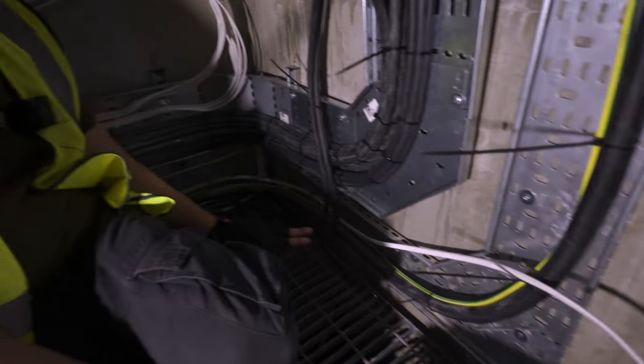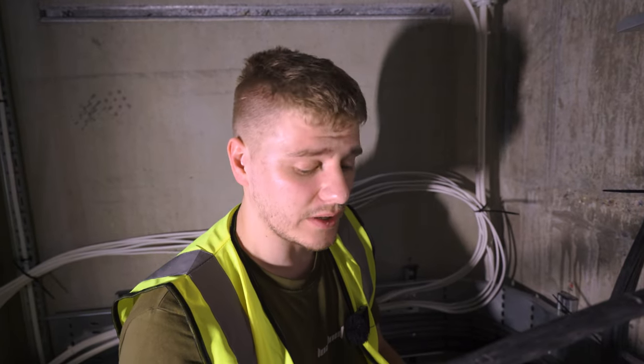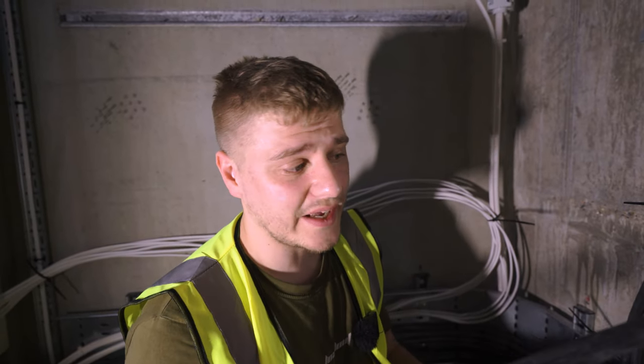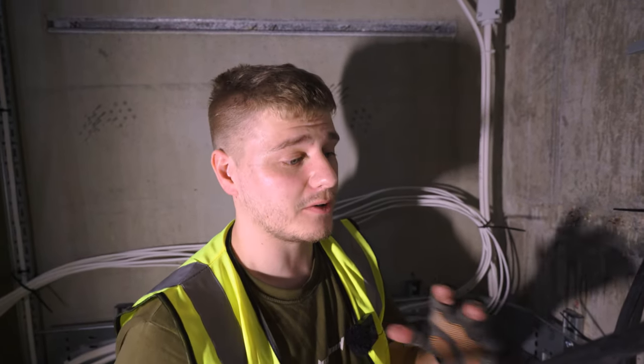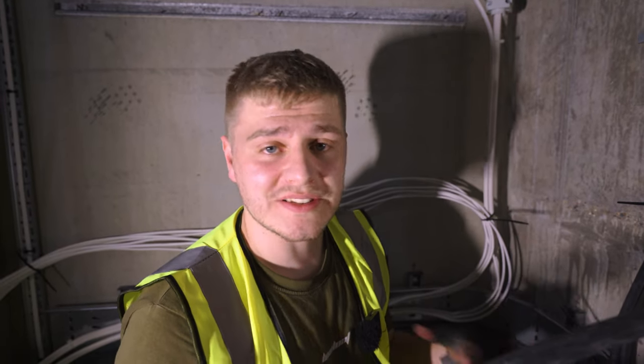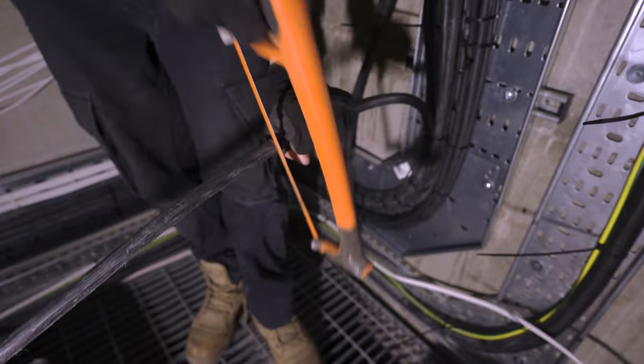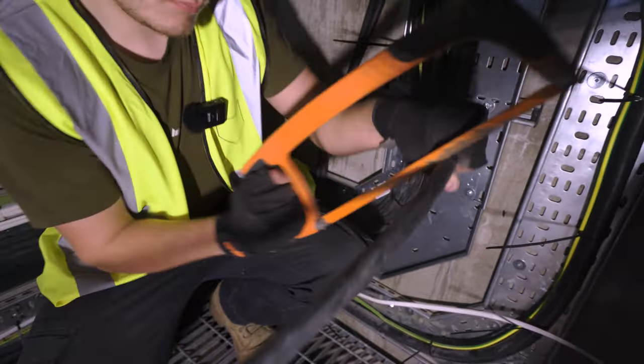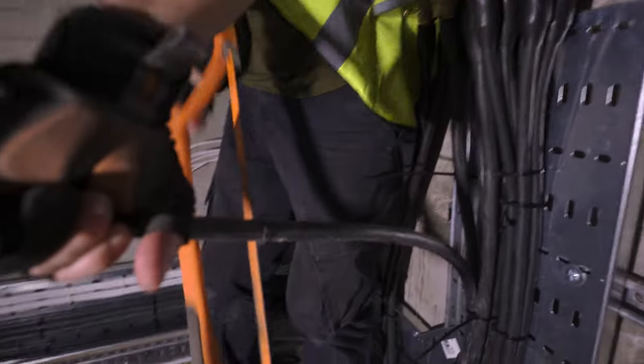It is over-swooping a little bit here, but we've actually got loads of room in the corner to push a bit of slack back, and that will be perfect. I didn't have to think about what I was doing — I could just crack on under pressure and achieve a nice gland using this technique. It's pretty clutch. It's great for big cables — actually more forgiving with big cables. I find with smaller cables like 25s it's easier to mess it up. There's a lot more tolerance with bigger cables — it's almost perfect.